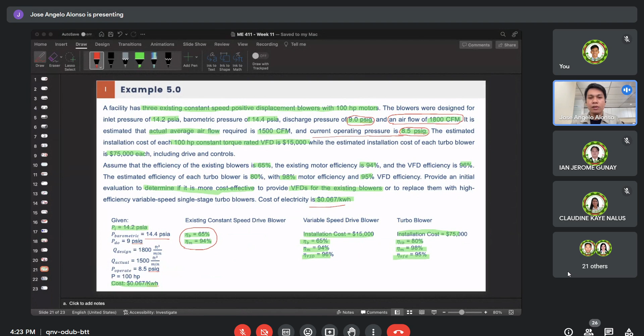So we divide the power we obtained, the isentropic work, by the blower efficiency of 0.65, and motor efficiency of 0.94. This gives us a power consumption of 69.7 kilowatts. This 69.7 kilowatts is now the direct power consumption, not the isentropic work anymore, not the power imparted to the air or gas. This is the direct power consumption since we already divided it by the blower efficiency and motor efficiency. So directly we can calculate from this how much electricity cost is consumed using this power consumption.